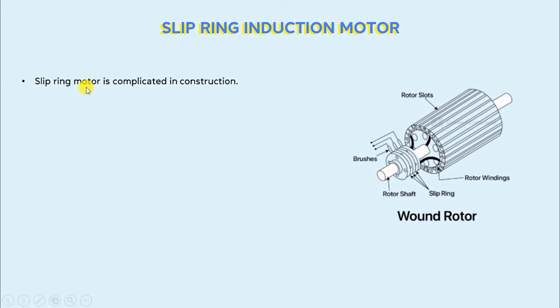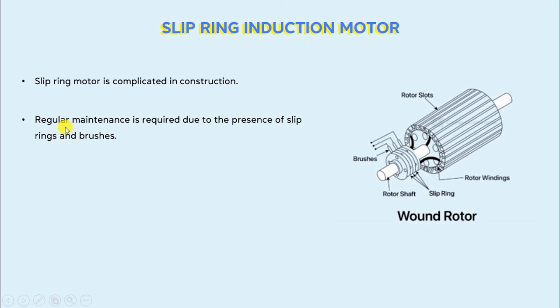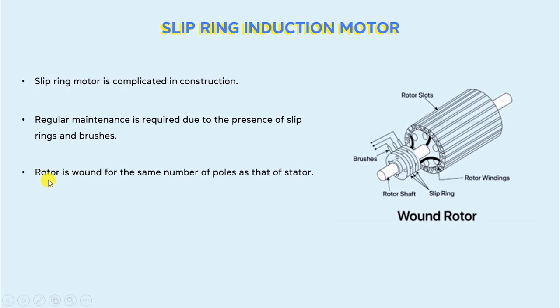First, we will talk about the slip ring induction motor. The construction of a slip ring motor is complicated due to the presence of slip rings and brushes. Moreover, regular maintenance is also required in a slip ring induction motor due to the presence of slip rings and brushes. The rotor of a slip ring induction motor is wound for the same number of poles as that of the stator, so the number of poles in the stator and rotor of a slip ring induction motor is the same.